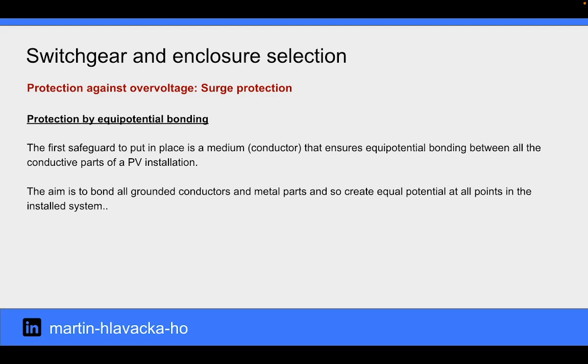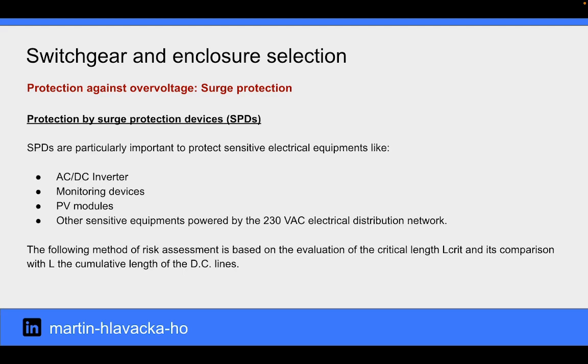The first safeguard to put in place is a medium that ensures equipotential bonding between all the conductive parts of a PV installation. The aim is to bond all grounded conductors and metal parts and so create equal potential at all points in the installed system. SPDs are particularly important to protect sensitive electrical equipment like PV inverter, monitoring devices, PV modules, and other sensitive equipment powered by the 230 VAC electrical distribution network.